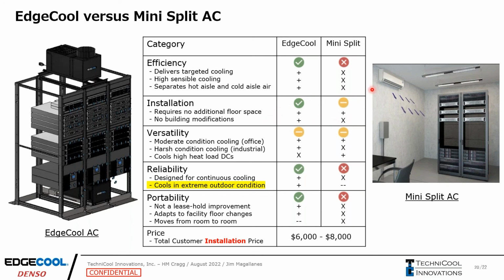So with a mini split system, you're putting the condenser unit outside the building. So you're going through exterior walls, roofs, all places where leaks can happen, just a little bit harder for that installation. Versatility, we're cooling down office spaces. We're cooling down harsh conditions in industrial systems. They'd have to build a small room to cool down an industrial space, so that's not really a benefit of that. We only have the 1.5 ton coolings for our EdgeCool right now, so we use that as a negative. They have multiple systems that cool down 1 to 5 tons of cooling, so that's a plus.